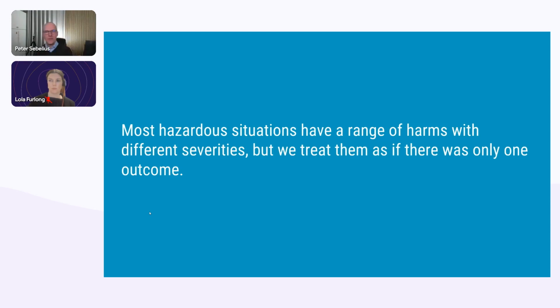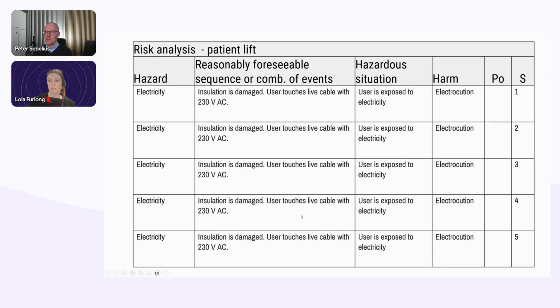This is the problem. I believe that the true representation of this risk and the probabilities would be something more like this. We have some people with really thick skin, completely dry hands, rubber shoes, not touching anything else, touching the cable. They would feel it. Maybe it's a 1 or 2. We have those more normal cases where it's significantly painful, but nothing more happens. 4, that would be the ones that have to get resuscitated with a defibrillator or get an atrial fibrillation and need to go to the hospital for a check. And 5, the unfortunate ones that would actually die. And I think we could say that all of these things could happen as the result of this hazardous situation. But what severity should we then use? We should not use the average, I can tell you that much. That would be completely inappropriate.